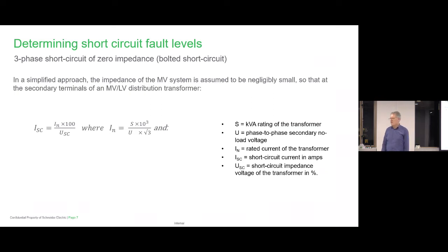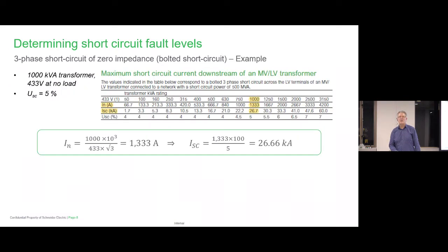Determining the short circuit fault level. This is a nice little formula, which you've probably seen back in your engineering days, but it's still valid today. I'm not going to go into great detail on all of it, but you can see this is the nominal rating, the current of the transformer. S is the kVA of the transformer times 10 to the power of 3, over voltage and √3. And once you use that, I'll move on to the next slide, you'll see what it can look like.